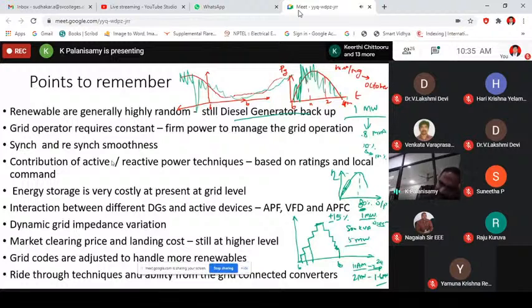When the grid impedance is highly dynamic or highly varying because of the configuration, because n numbers of solar PV inverters are connected and disconnected at instant to instant, the third L, it means the LCL, that L is highly varying. If that is varying, your active power filter or your VFD or your solar inverters will not maintain good power quality to the grid, right? So that will also be an additional burden to the grid.